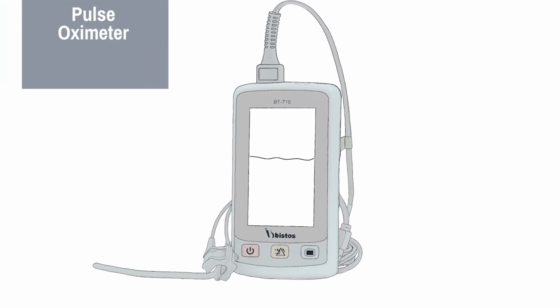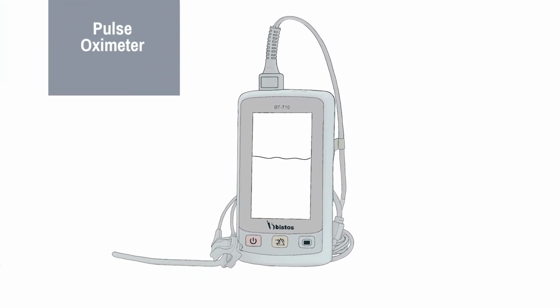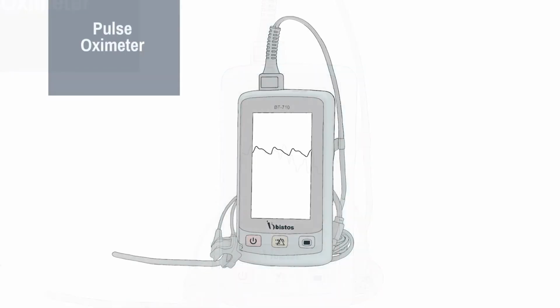You may also get a poor reading if the baby is moving around a lot. Waves affected by motion tend to look like this. Make sure that there is no strong outside light source shining onto the probe. That can also interfere with the readings. Once you have a steady waveform, the saturation reading and heart rate should also settle.